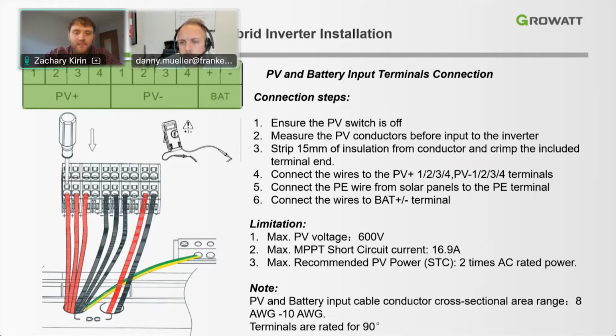The max recommended PV power is 2 times the AC rated power. For a 10 kilowatt system, you could install 20 kilowatts worth of array. And this is really fantastic. The DC to AC ratio being 2.0 gives more accessibility to different system installations. Another note, the PV and battery input cable conductors' cross-sectional area must be between 8 and 10 gauge wire. And those terminals are rated for 90 degrees. For when you're doing your calculations for derating, those terminals are rated at 90 degrees.